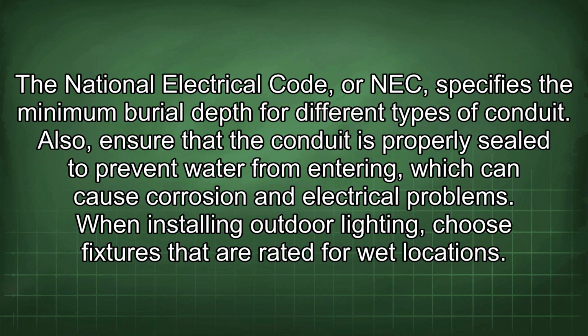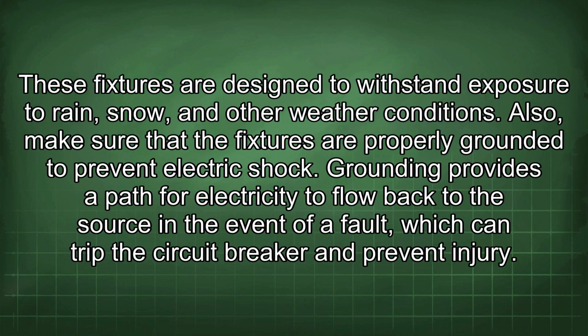When installing outdoor lighting, choose fixtures that are rated for wet locations. These fixtures are designed to withstand exposure to rain, snow, and other weather conditions. Also, make sure that the fixtures are properly grounded to prevent electric shock. Grounding provides a path for electricity to flow back to the source in the event of a fault, which can trip the circuit breaker and prevent injury.